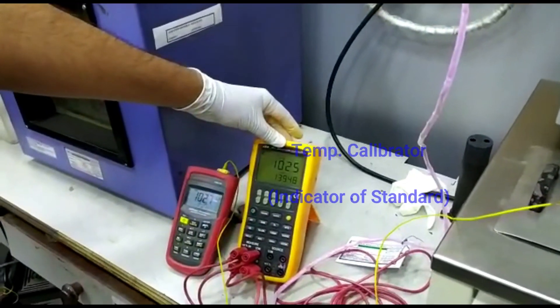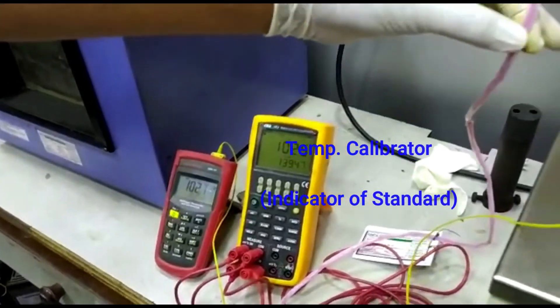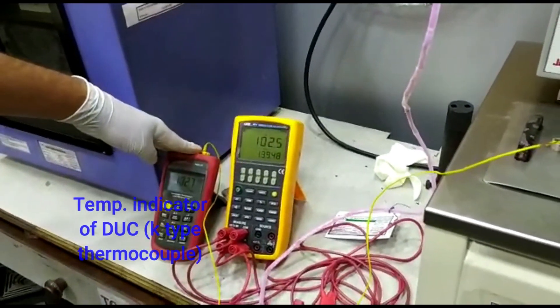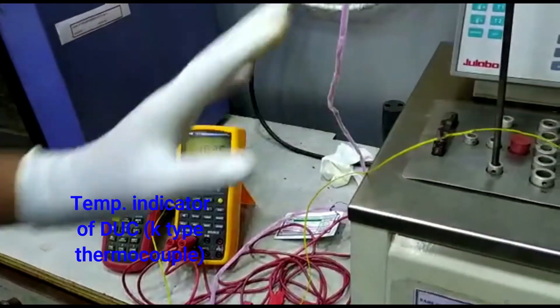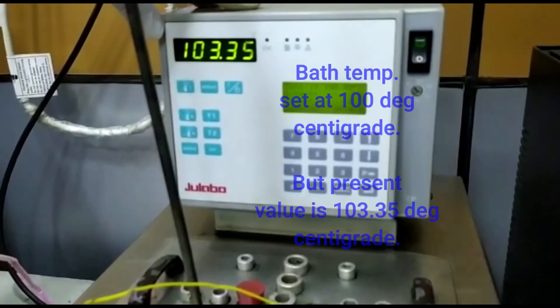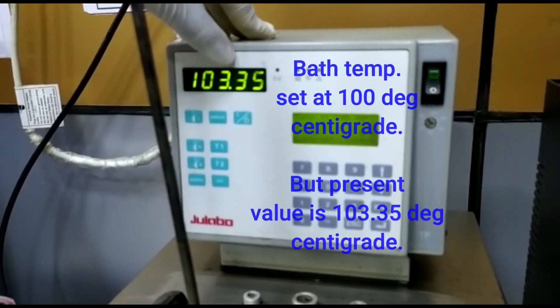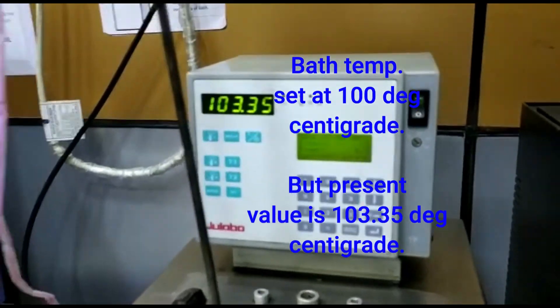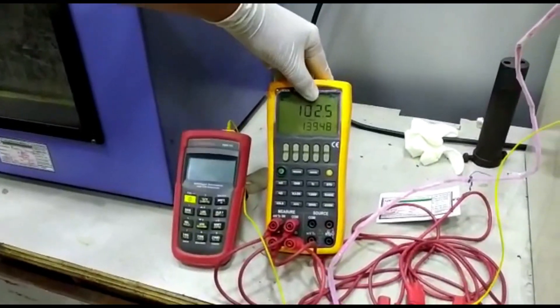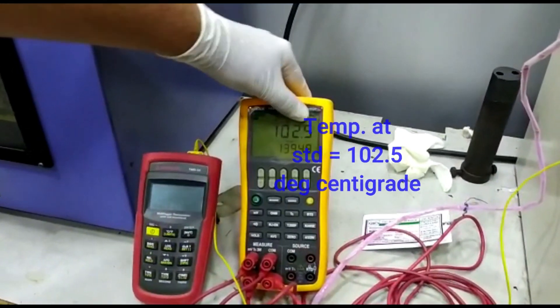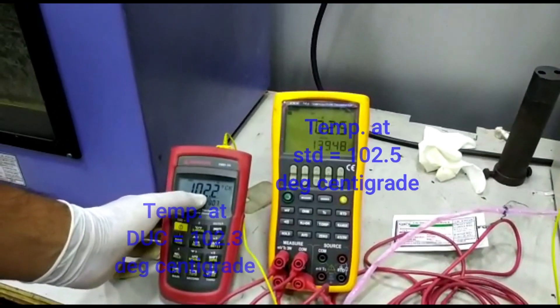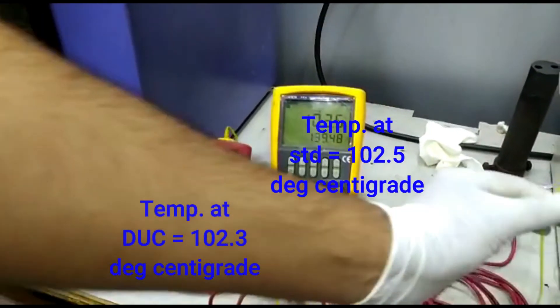This is our temperature calibrator by which we will get the reading of our SPRT and this is the digital thermometer to get the reading of this K type thermocouple. Now we set the temperature of this bath at 100 degree C and the bath is showing this temperature of 103 degree point 35 degree C. And now we can see the temperature showing this temperature calibrator is 102 point 5 degree C and this temperature meter is showing 102 point 3 degree C. This is the DUC.